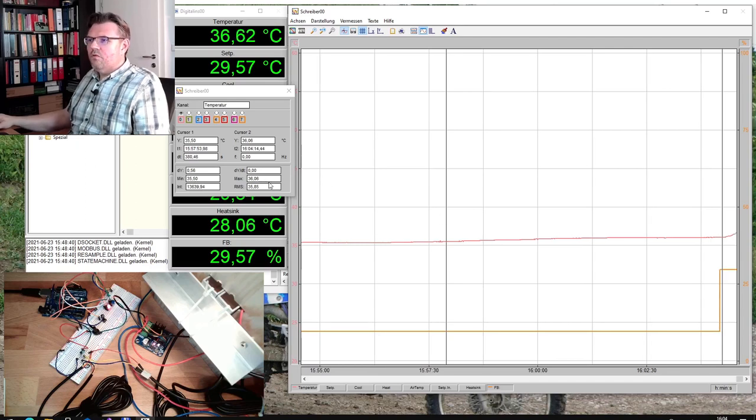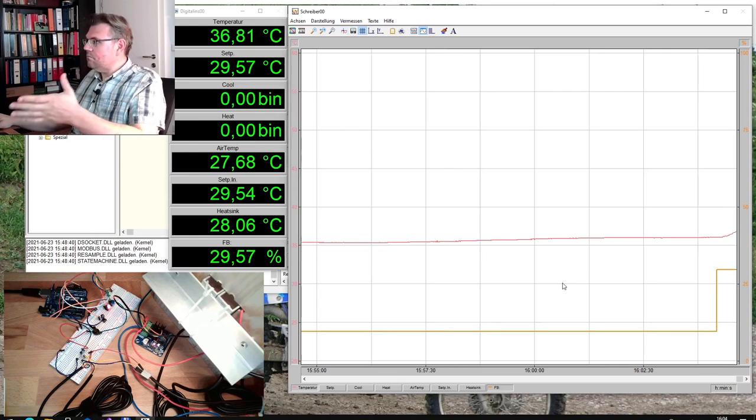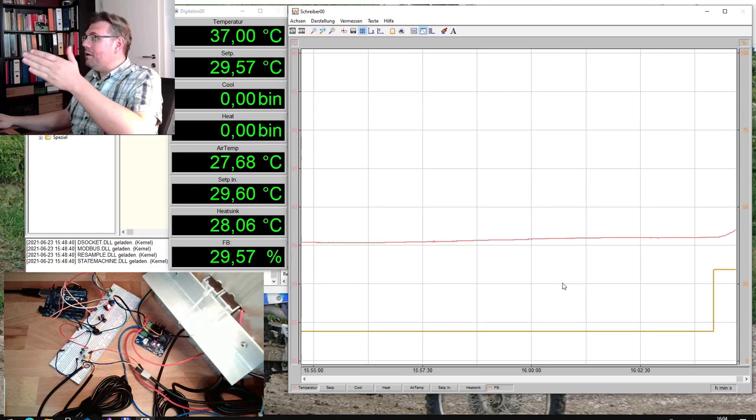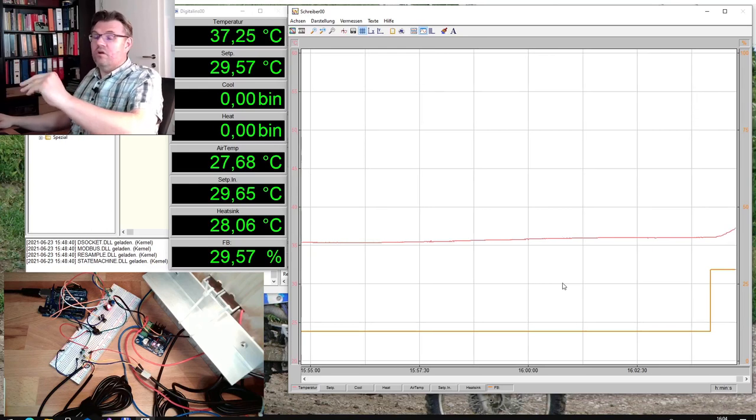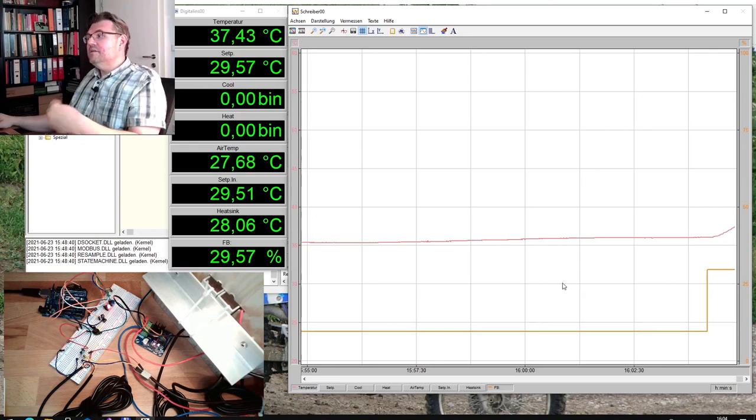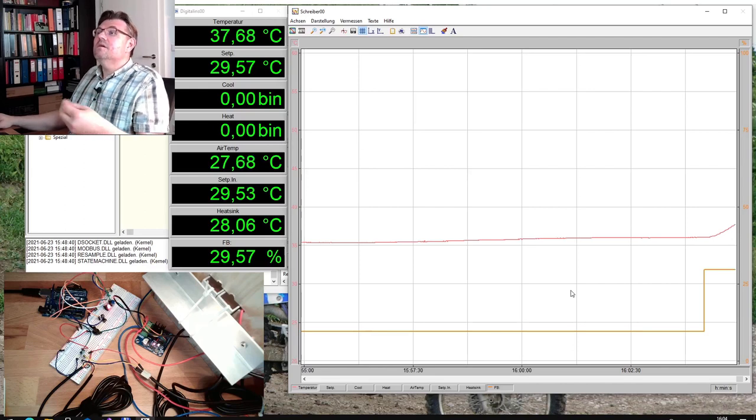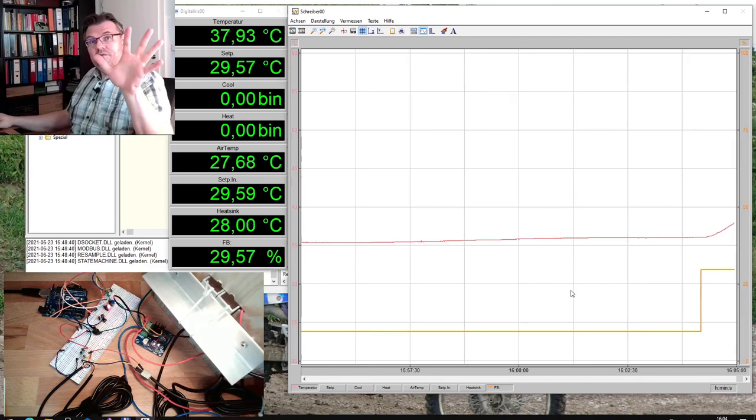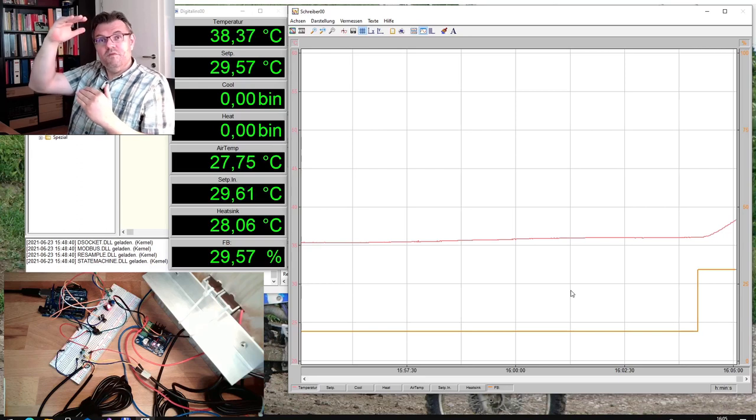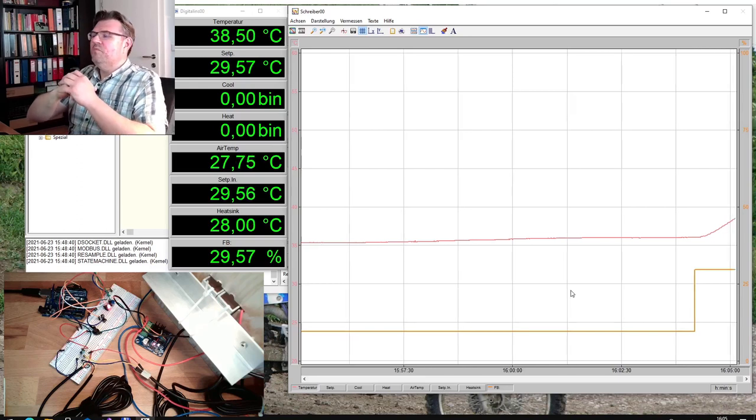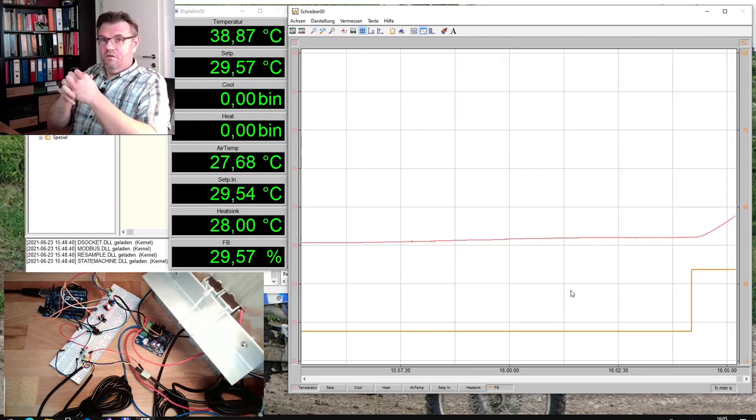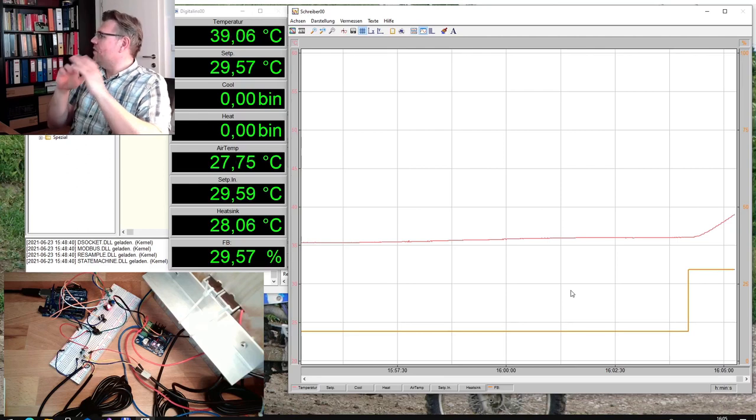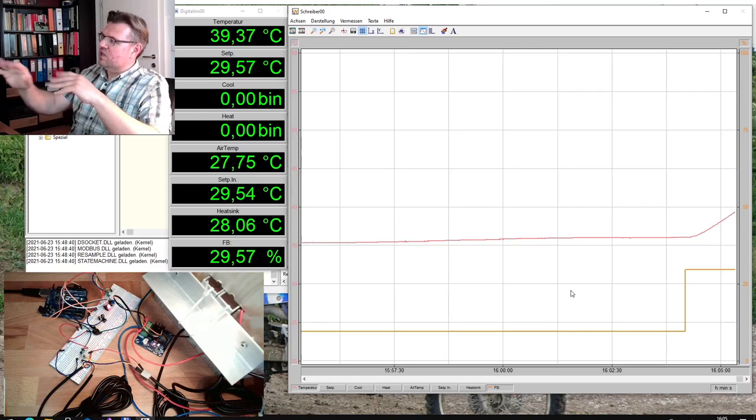You see it reacted, now 29.5, so 20 percent more correcting variable. We will see how the temperature here is reacting. It was 36 degrees and now we're waiting. By the way, internally this thing is calculating with percent, the correcting variable is given in percent, and temperature: 5 degrees is zero percent and 55 degrees is 100, so we have a span of 50 degrees. This is later important if we calculate the gain factor of the system.